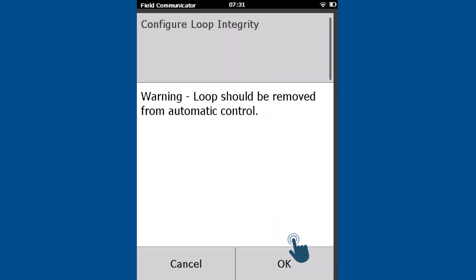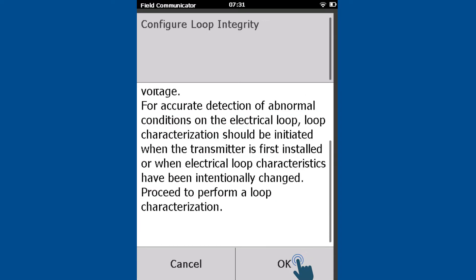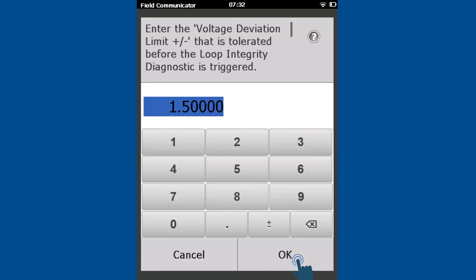Read and acknowledge the warning message. This step baselines the voltage and resistance of the electrical loop for the transmitter to learn what proper operation looks like. Enter a voltage deviation limit — if this voltage value is exceeded, a diagnostic notification will be triggered. We recommend using the default provided.